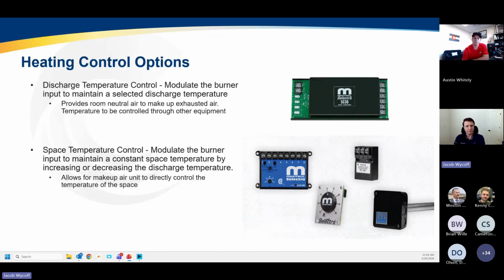And when you're taking a look at these makeup air applications, a few things that you want to think through early on is how do you want to control your discharge temperature? So one option would be discharge temperature control, where you modulate the burner to maintain a select discharge temperature. For makeup air applications, this would typically mean providing neutral air to the space and then either specific space temperature is not a huge concern, or you have some auxiliary equipment that's actually controlling the temperature within the space.